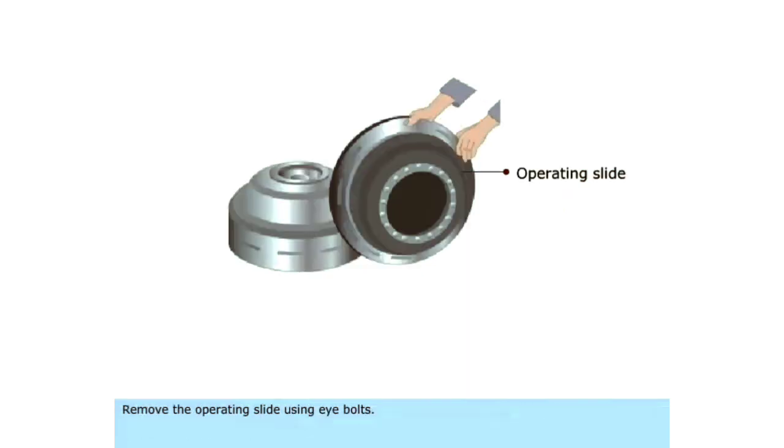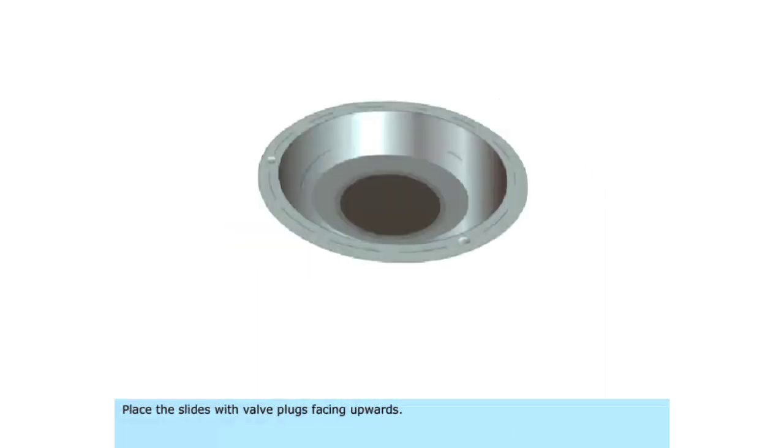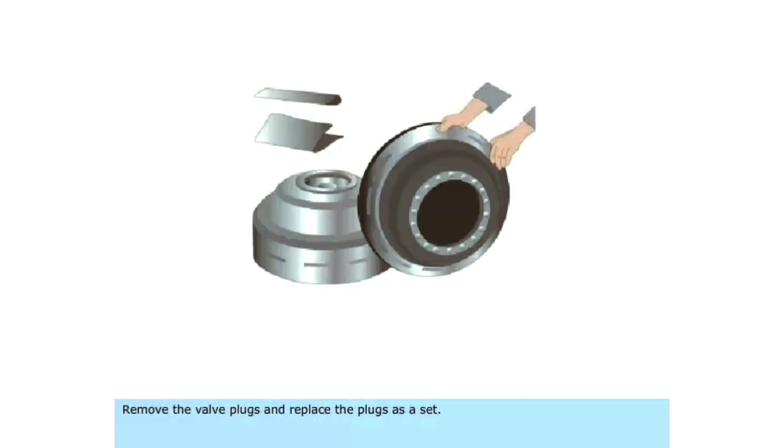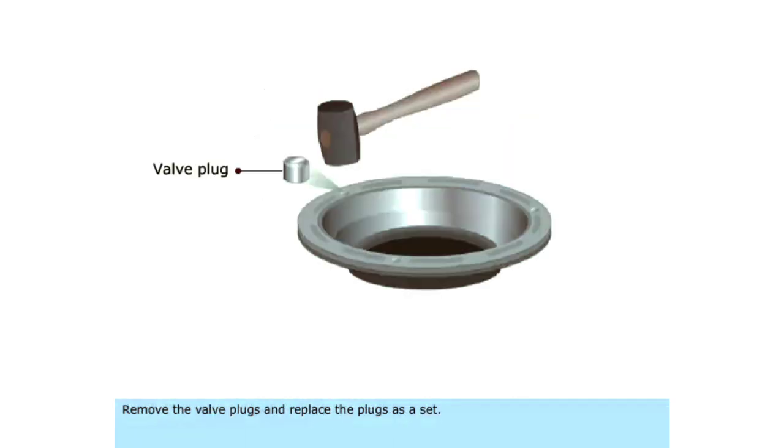Remove the operating slide using eye bolts. Place the slides with valve plugs facing upwards. Remove the valve plugs and replace the plugs as a set.